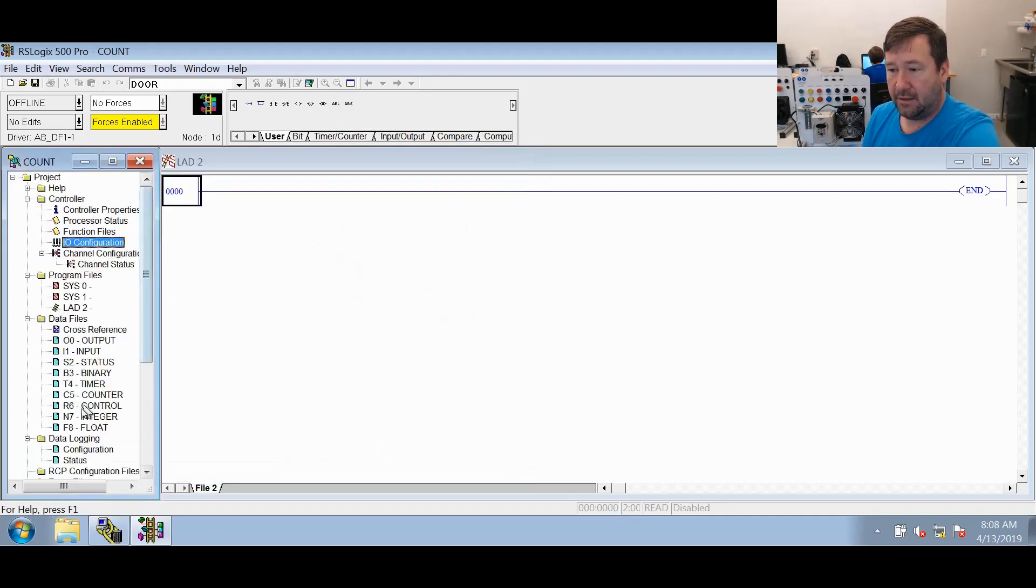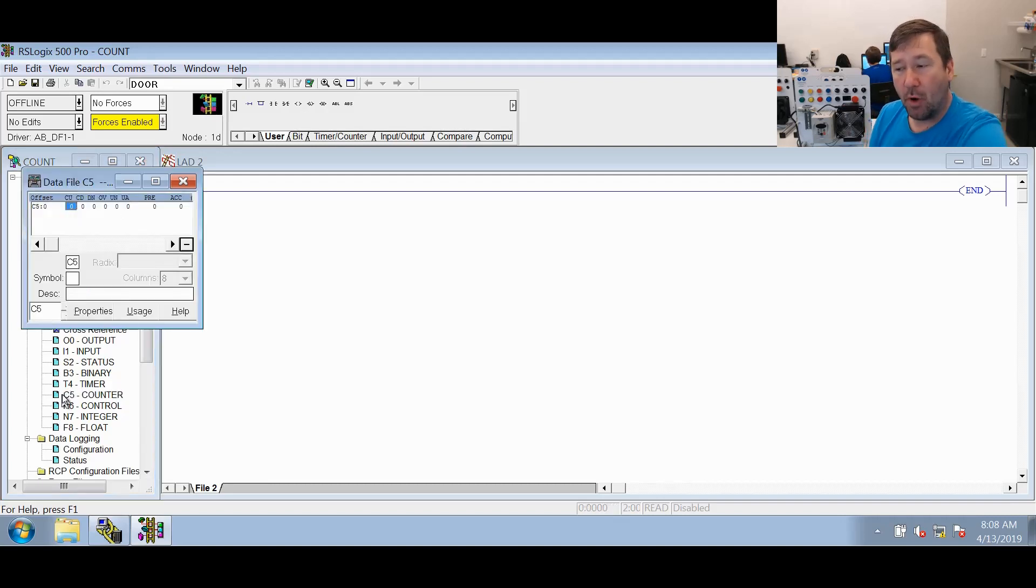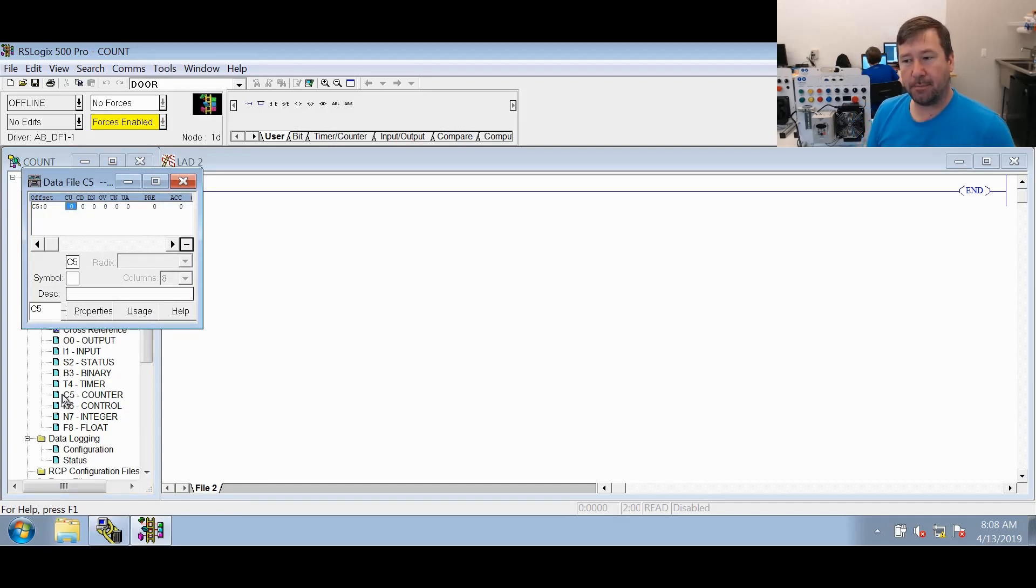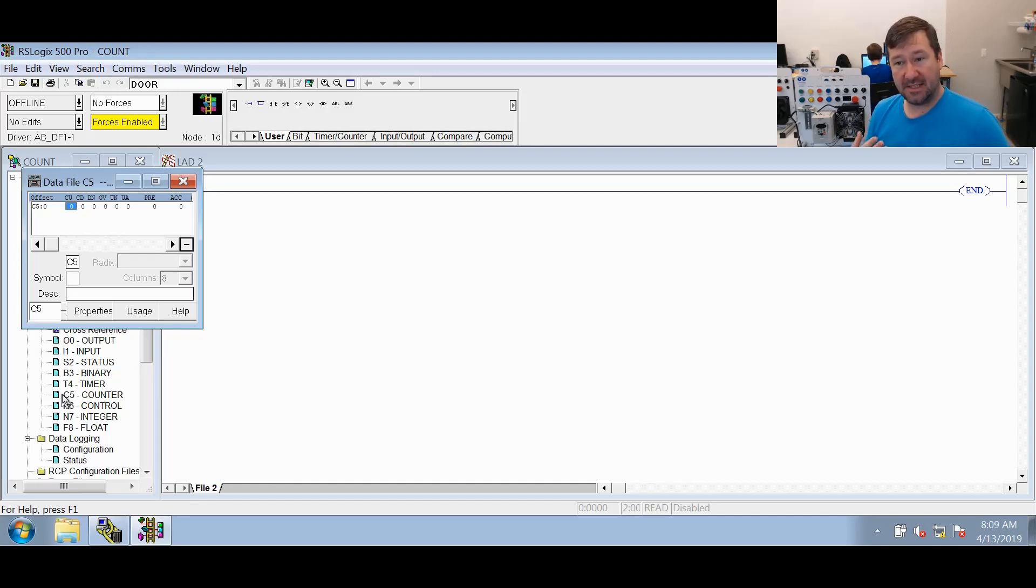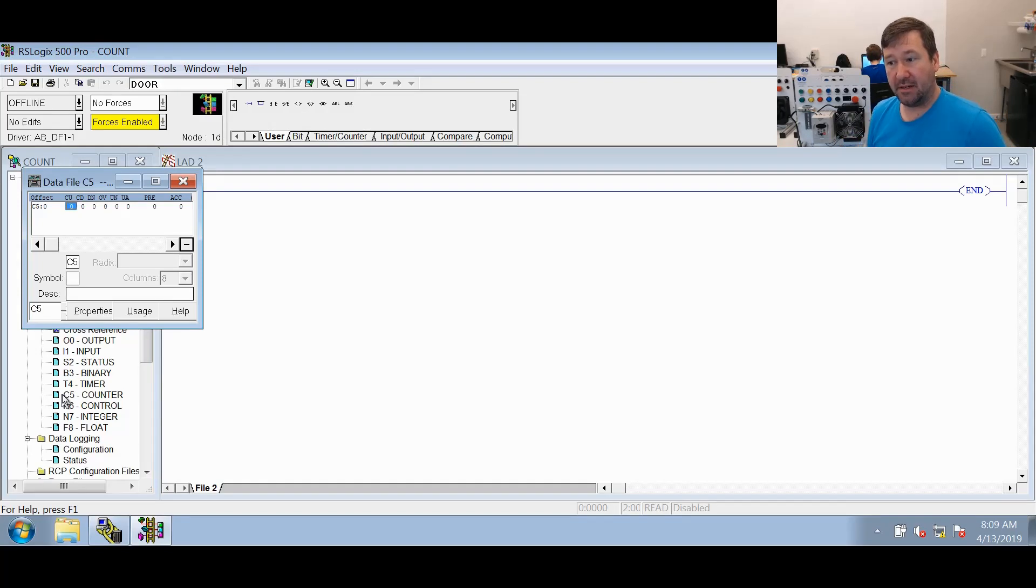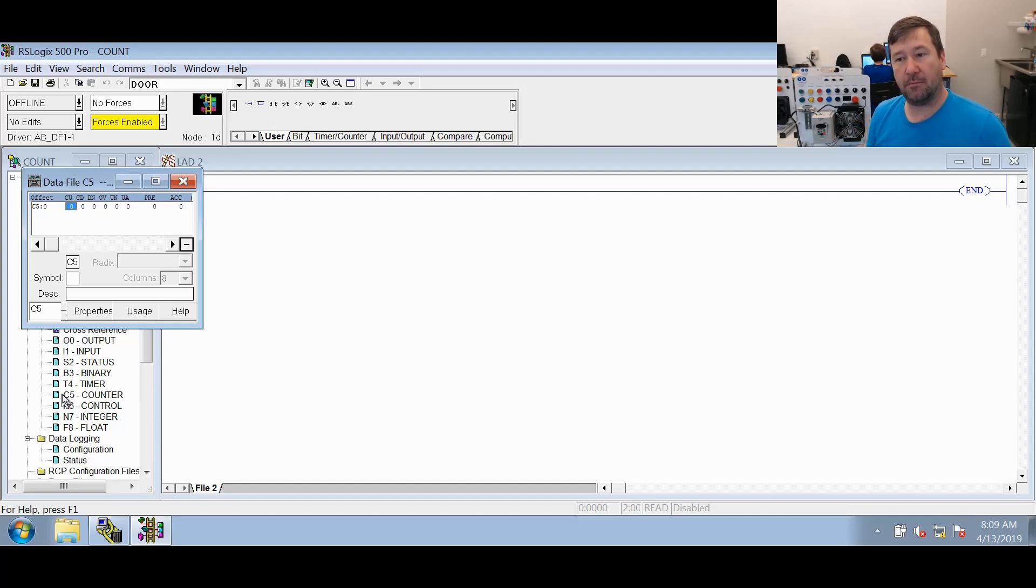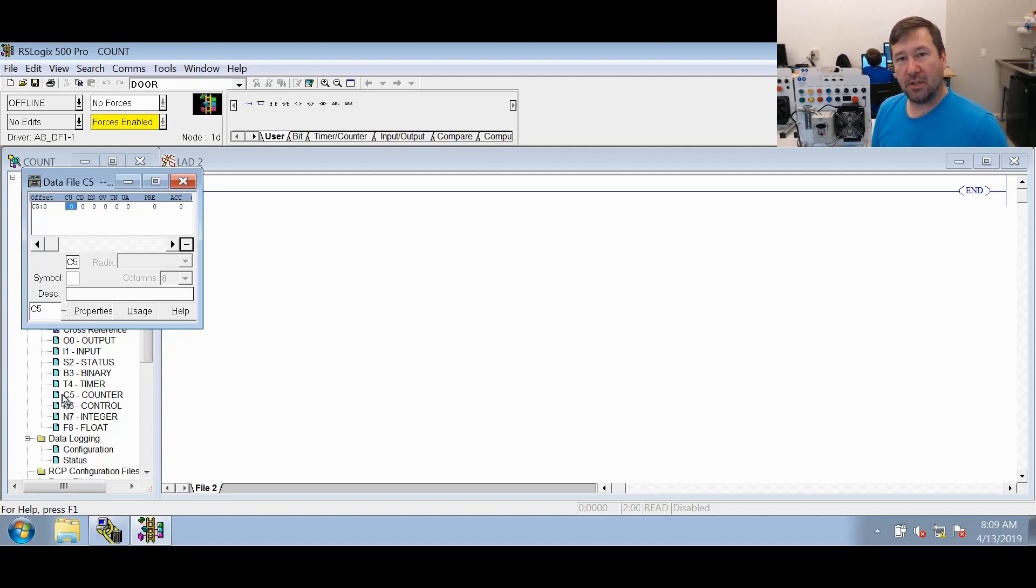Now let's open up the C5 counter data table and just have a look to start with to see what bits we actually have. So we have the CU bit which is the count up enabled bit, the CD bit which is the count down enabled bit, the DN bit which is the done bit, the OV bit which is a count up overflow, the UN bit which is a count down underflow, and then we have the UA bit which is the update accumulator bit.